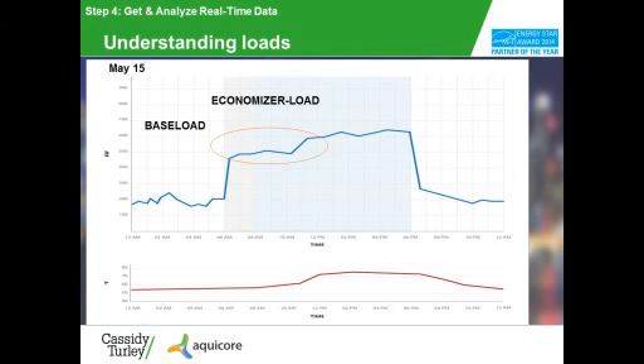So now I'll show you the line where the temperature finally reached 63 degrees. That's the break point at this building where mechanical cooling is enabled. So the outside air temperature hit 63, and it enabled the mechanical cooling system to come on. And now we get to see the load increase. The mechanical cooling is kicking in. More people were occupying the building. So the load is just gradually coming up in the afternoon, and it's a typical day. So now we've kind of reached that typical day. We're still not using electric heat, so we're using mechanical cooling. We're not using any heat at the building, and now we're running at full load.